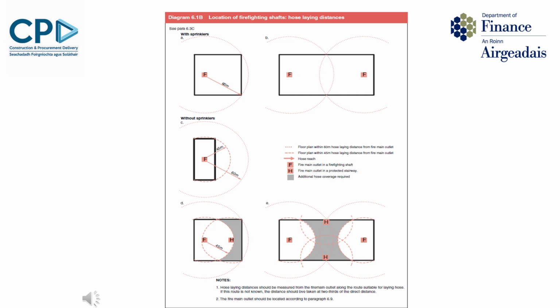Figures C, D and E are buildings without sprinklers, and hence the additional criteria of being within 45 metres of a fire main outlet applies. So for figure C, the one firefighting shaft satisfies both criteria, i.e. all parts of the floor are within 60 metres of a fire main in a firefighting shaft, and all parts of the floor are within 45 metres of a fire main, either in a firefighting shaft or in a protected stairway.